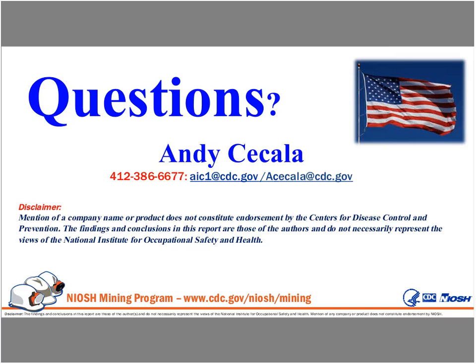So we feel the key is, and as I showed in the presentation, when we recommend the use of mechanical filters, as the filter develops that dust cake, it's more effective. For instance, at the silica sand operation, a year later, the protection factor went from 8 up to 25. So that's where we recommend, if you look at the pressure and the airflow, that will provide the best indication on when the filter needs changing. Again, you don't want to change the filter until your airflow drops down to a level that it's not sufficient for pressurization or for the CO2 issue.